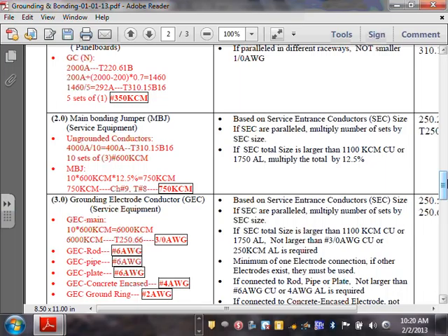So that's your main bonding jumper. If you parallel that, let's say daisy chain them all together, think about it. I don't know anything in the code that says you cannot parallel them. So if you cut them by half, so 750, and then size appropriately going up. Does anybody know any location which says you cannot parallel a main bonding jumper? You're paralleling, basically. It's not a good idea though.